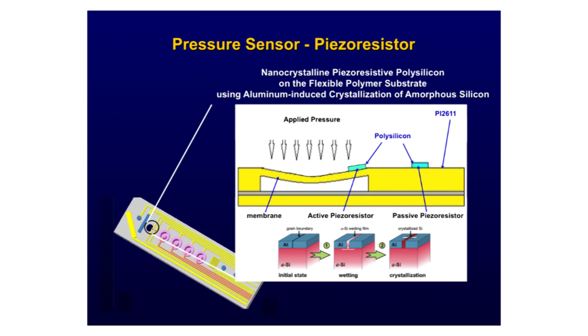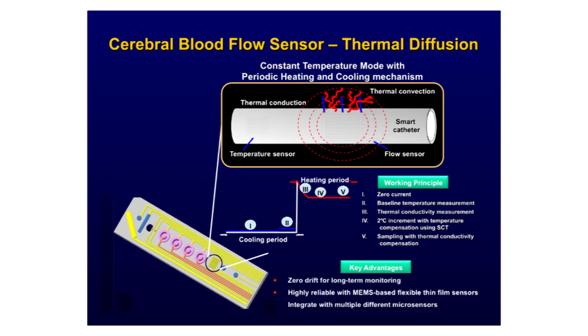For cerebral blood flow, we've used a thermal diffusion mechanism where you heat the coil in one place, and you see how long it takes for the temperature to drop on a second sensor. And the more rapidly the temperature drops, the more blood flow there is. It's sort of a washing out principle, as I understand it. So that's the technology used for local blood flow. Remember, this will only look at the blood flow perhaps for a cubic centimeter around the catheter. This will not tell you what the blood flow is in the whole hemisphere or in a more global sense.